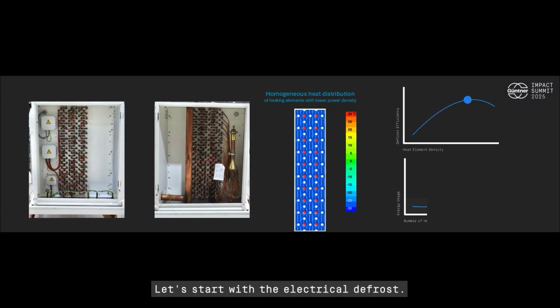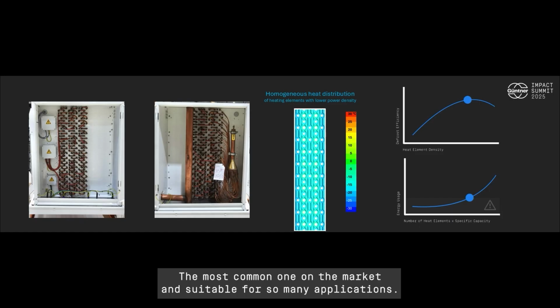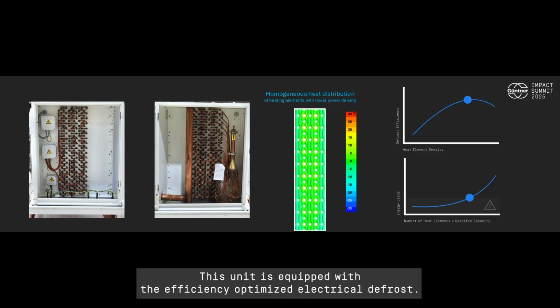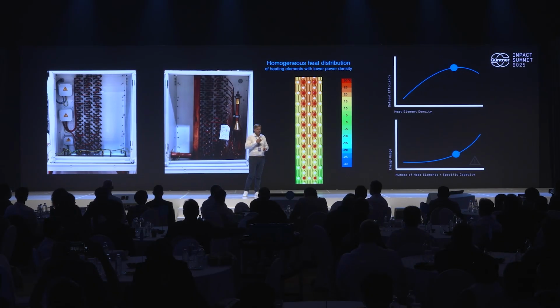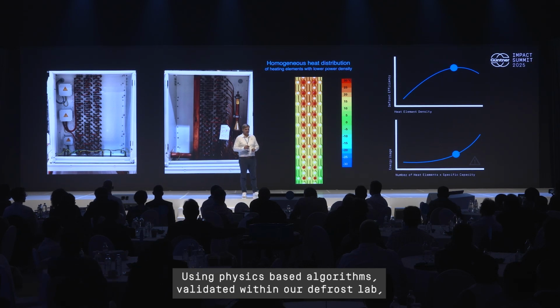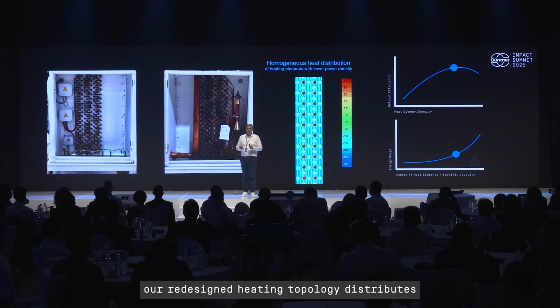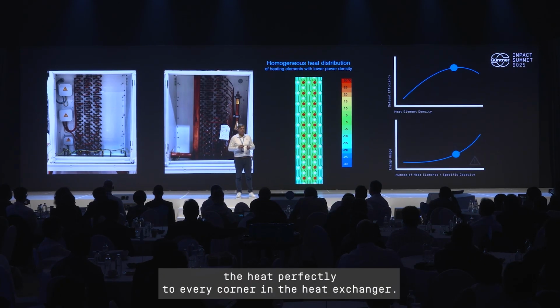Let's start with the electrical defrost, the most common one on the market and suitable for so many applications. This unit is equipped with the efficiency optimized electrical defrost. Using physics-based algorithms validated within our defrost lab, our redesigned heating topology distributes the heat perfectly to every corner in the heat exchanger.